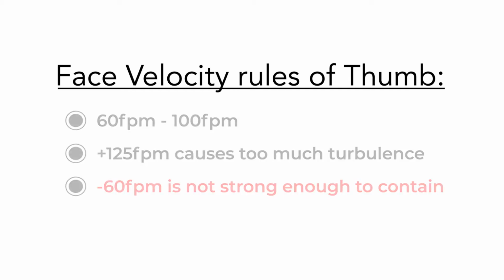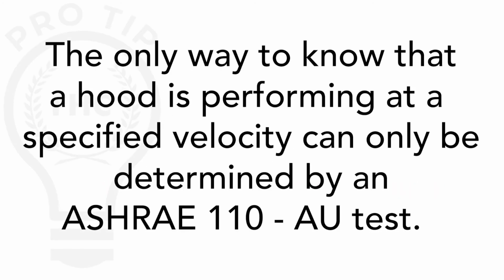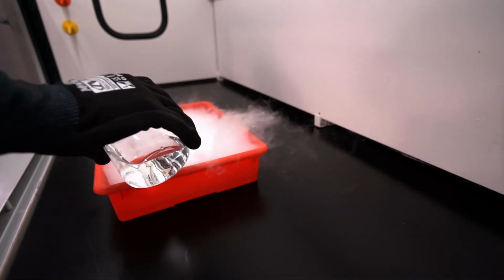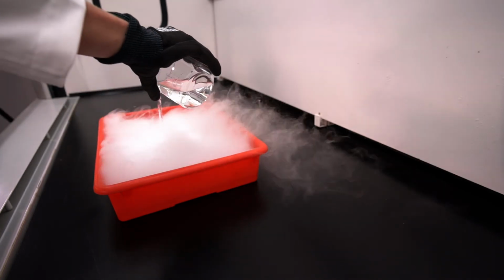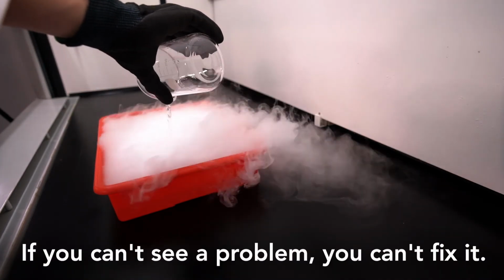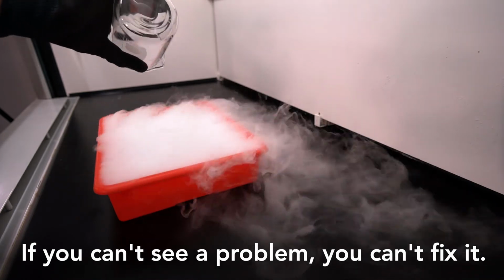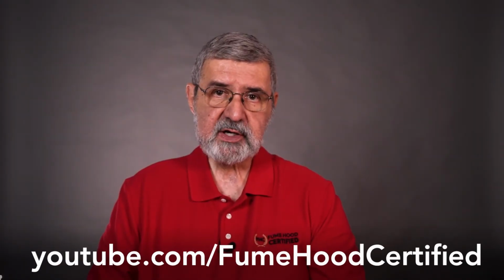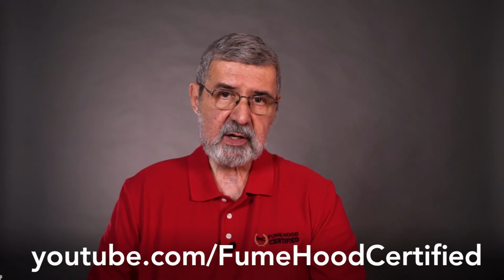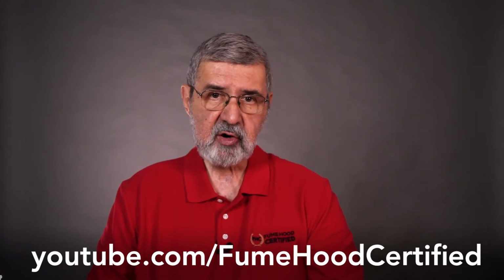Again, the way you know a fume hood is performing at a specified velocity can only be determined with an ASHRAE 110 as-used test. It often helps to visualize airflow within the hood. Not everyone has access to a fog machine, so another way to visualize airflow is to pour warm water on dry ice. It is often said that if you can't see a problem, you can't fix it. Fume Hood Certified is starting to post videos on our YouTube channel that will help you visualize some of the issues we are discussing.